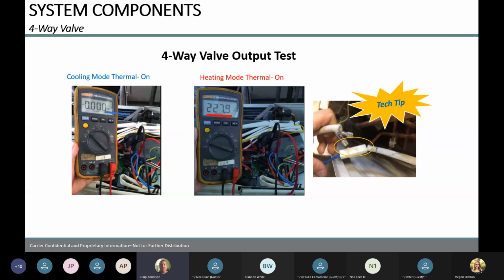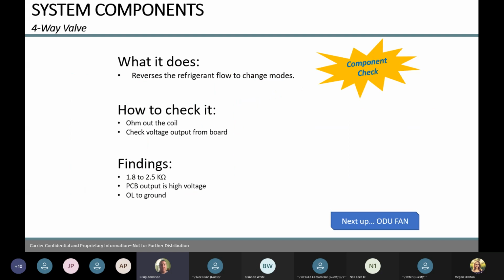But reversing valves, it's a 220 volt reversing valve, energized in heating. What the reversing valve does is change the flow from cooling to heating. It also switches over when we go into a defrost: it's going to switch the unit into cooling to melt the ice off outside and go back after that is done. You can ohm out the coil on the reversing valve as well to see if the ohms are good, or we check the voltage from the board to the reversing valve to see if we have 220 volts in heating mode.